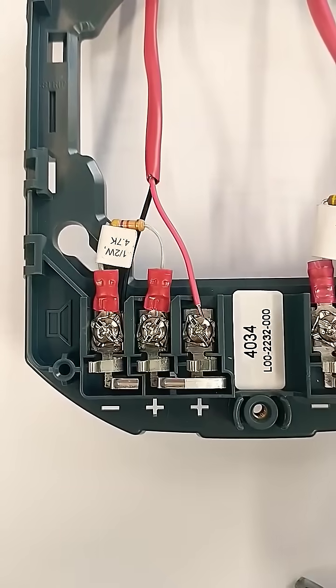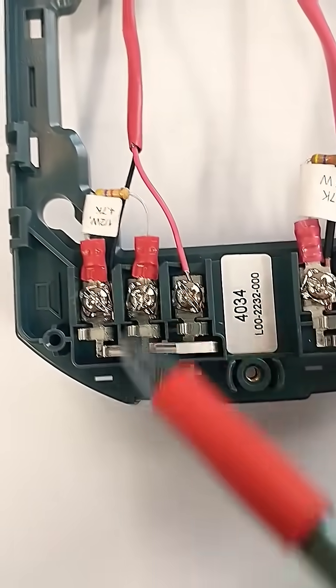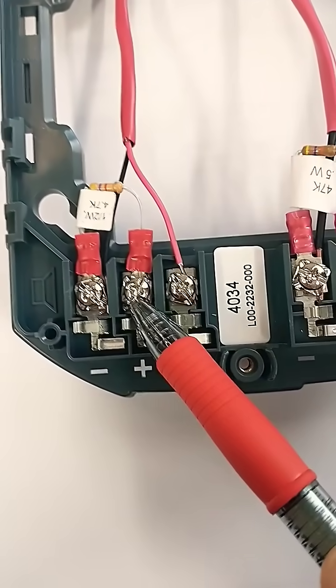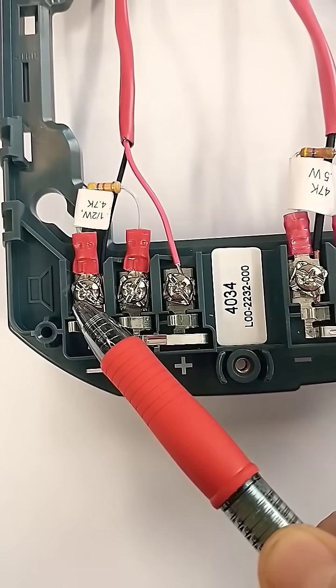At the end of your speaker circuit, you're only going to have one cable coming in, so you'll need the end-of-line resistor installed. Make sure it goes in between the empty plus terminal and along with the negative wire.